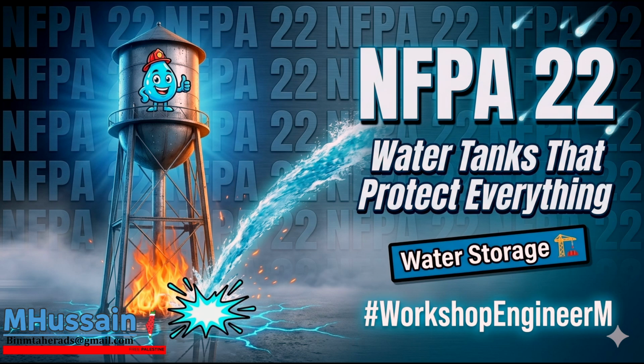And the dead load we're talking about is staggering. Water weighs roughly 8.34 pounds per gallon. If you design a 100,000-gallon elevated gravity tank, you have over 830,000 pounds of water, plus the weight of the steel itself sitting high in the air.